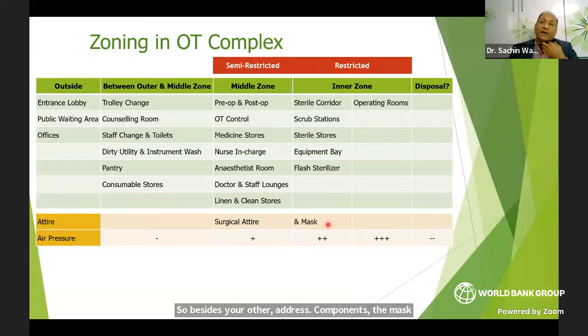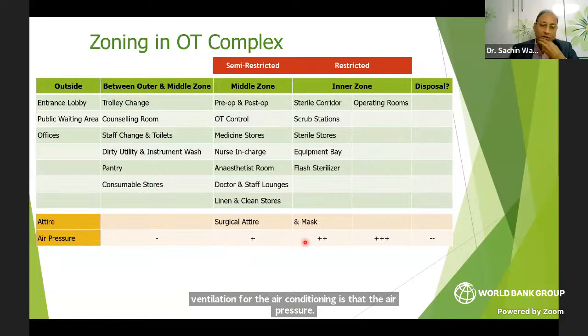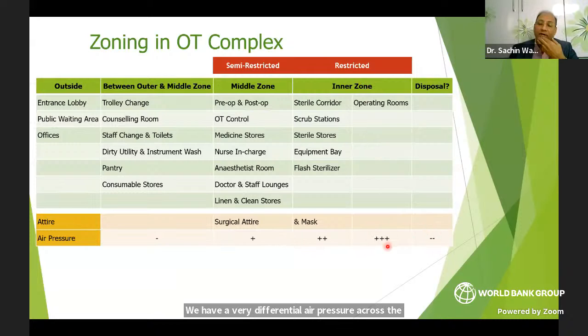How this translates for the ventilation and air conditioning is that we have a very differential air pressure across the zones. You would have a very high pressure zone in the operating rooms, a relatively positive pressure in the sterile corridor, a little less in the middle zone, and a negative pressure in the outer areas. The purpose is that the operating rooms are supplied with filtered air under pressure, so there is no contamination from the other direction. This way we achieve unidirectional flow of air.